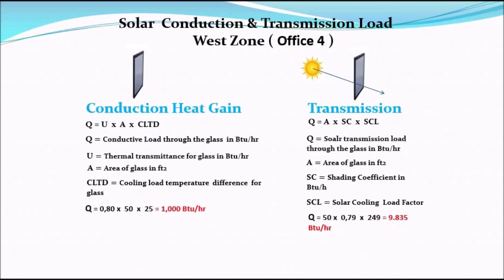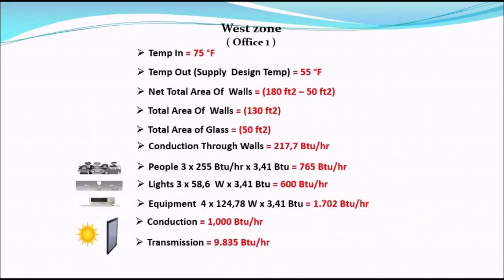For the west zone offices — number two, three, and four — and the east zone, we use the same formulas to determine the conduction and transmission loads in the same way as we did for office number one, based on the R-value, U-value, shading coefficient, and orientation. The next step is to select the outdoor and indoor design temperatures. In this example, the indoor design temperature is 75°F and the supply air design temperature is 55°F.